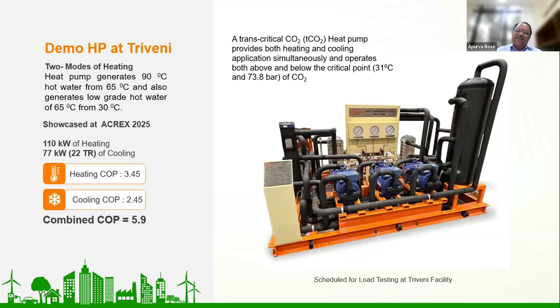Moving on, I just want to explain how it functions. This is still fairly self-explanatory. As I was mentioning, from the customer's point of view, he needs a heating and cooling solution, and heating here means 90 degrees or above. The one unit we have assembled can give heating up to 120 degrees Celsius. In fact, during our testing, we found it gave us 122 degrees Celsius, and cooling at 7 degrees Celsius, which I believe an HFC based system cannot provide at present because of the limitation of the refrigerant being used.